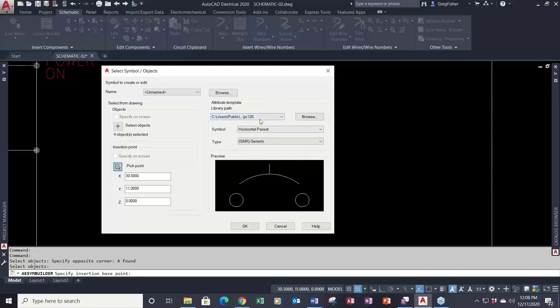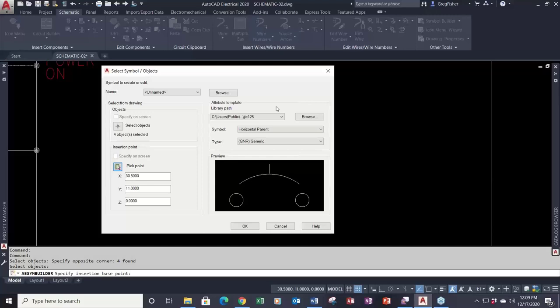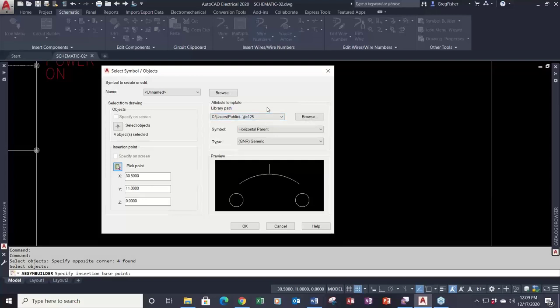After selecting objects and picking an insertion point — with snap on, which I highly recommend — there's a dialog that can be confusing. It has an attribute template library path. People confuse this with where the symbol will be stored, but that is absolutely incorrect. This path is only used for the template files used to insert attributes. Typically you don't have to worry about it because it defaults to whatever your project property library is set up for.